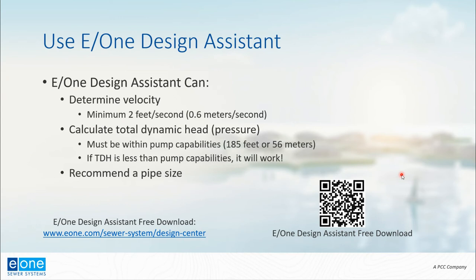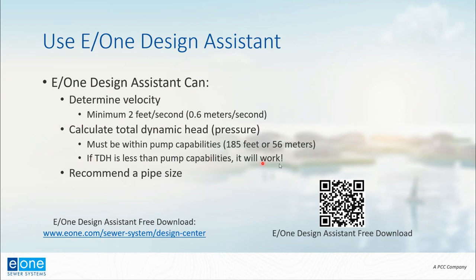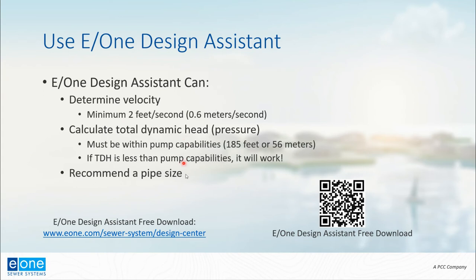With E/One Design Assistant, we are going to determine the velocity in the system. Really what we're looking for is two feet per second or 0.6 meters per second. The Design Assistant is going to help us calculate that total dynamic head, and ultimately what we need to know is what the total dynamic head is in the system. If the total dynamic head in the system is less than the pump capabilities, then the E/One pump is going to work, and all of this is also recommending a pipe size.